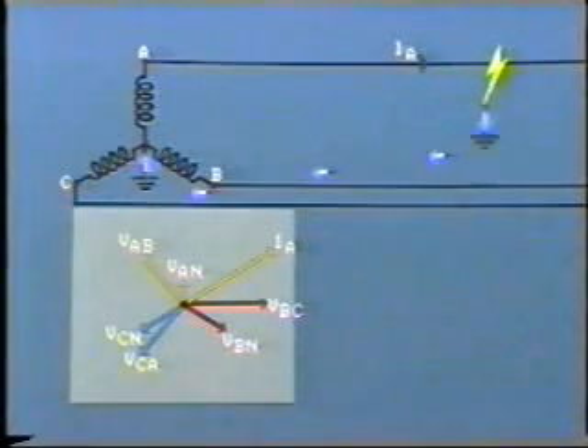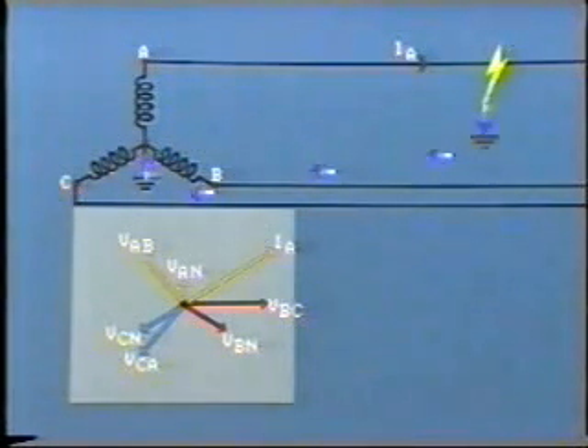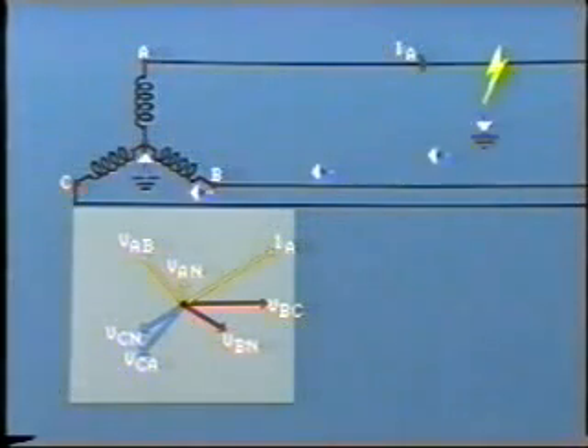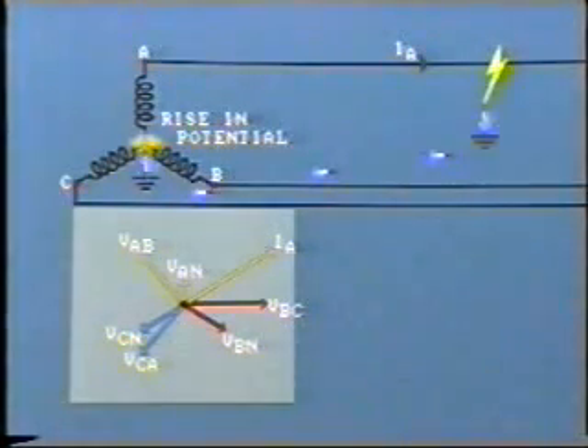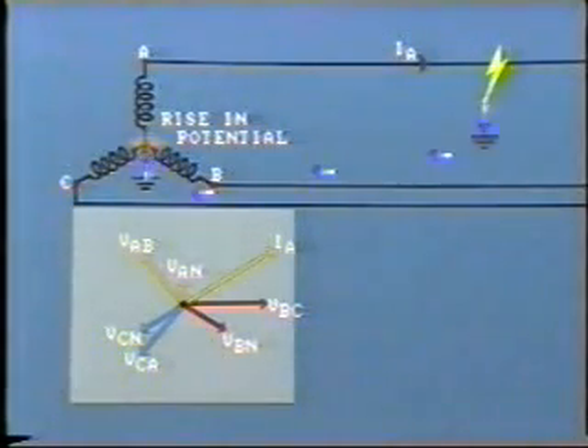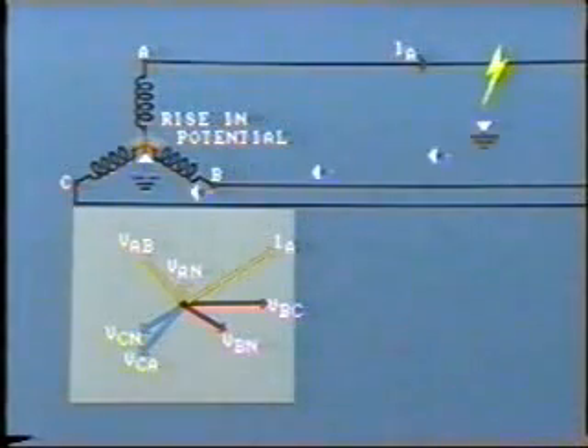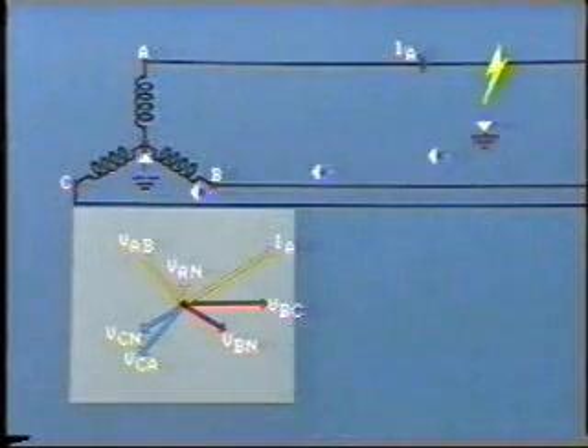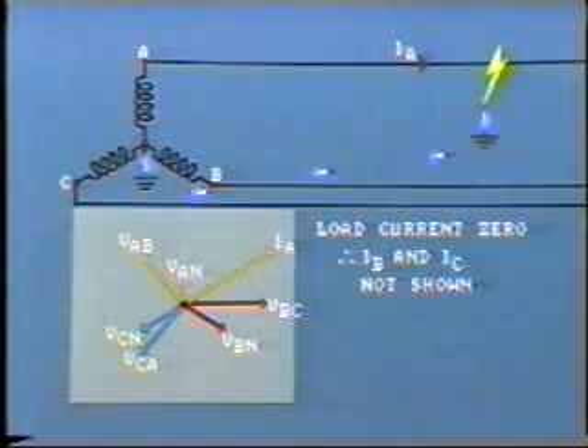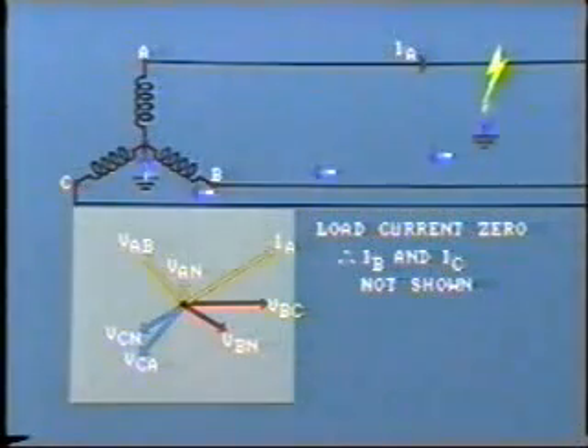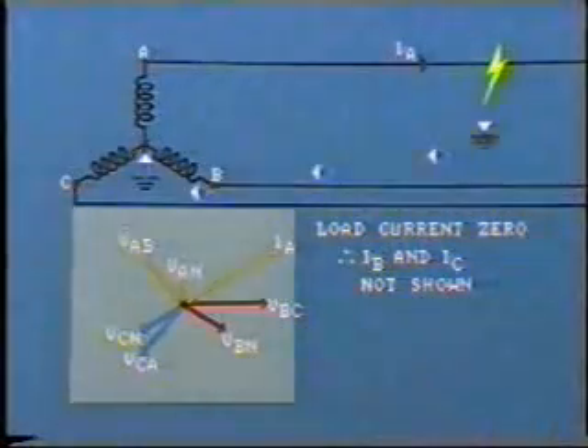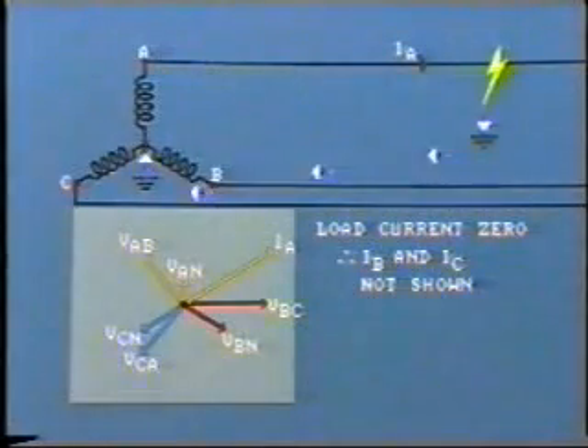The ground current will be high, as it is limited only by the impedance of the line and the return path to the grounded neutral. The flow of fault current through the ground path will actually cause a volt drop and a consequent rise in potential of the neutral at the source. This potential shift may be quite small, depending upon the actual grounding arrangements. As before, we are considering in this example that the load current is zero. Therefore, currents IB and IC would be zero, and they are not shown.